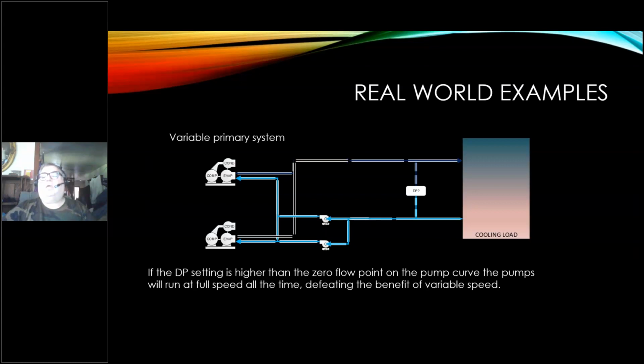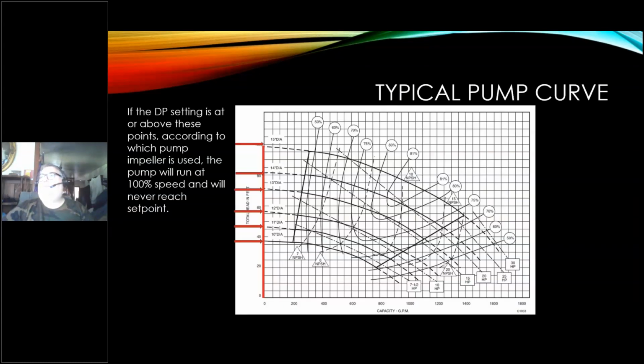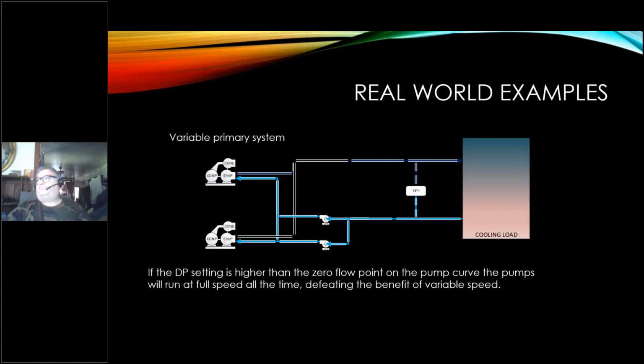Chris, can you just, for some of the folks, go back to where you were and explain the differential pressure sensor and how that is used? You just mentioned the DP, and some folks don't know what it is or why it's used. A typical control strategy is to vary the speed of the pumps based on the pressure differential out in the system. So that DP will show like 2/3 of the way down the system on a branch. So you've got some idea of how much pressure you've got, and that's where our 40% line comes into play, is that you want a pressure differential out there on the system, not at the pump.